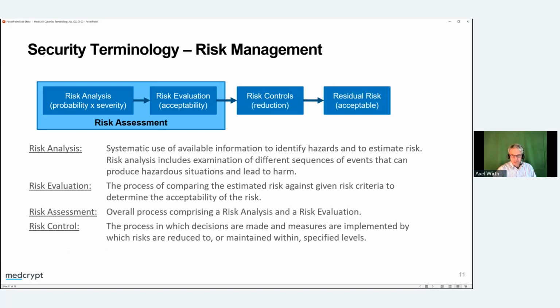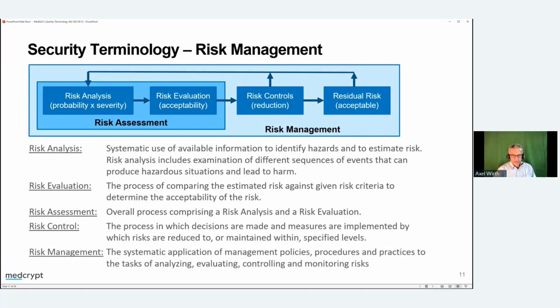And if it is not acceptable, I go back to the beginning and identify or re-estimate the risk and identify additional controls or new controls I may need to apply in order to get my residual risk down to an acceptable level. And clearly, this is not a one-time process. I should continually revisit that because risks change, new threats develop, new vulnerabilities become known. There may be a new use case for my device. I may be doing something with it that it was not the initial intended use of the device, and so forth. So there are many reasons why risk management should be a continual process rather than just a thing I do once during the design and development process.